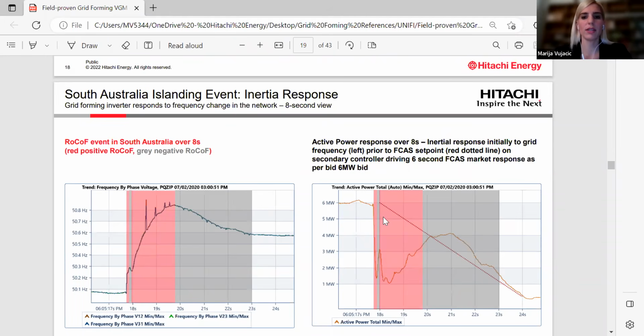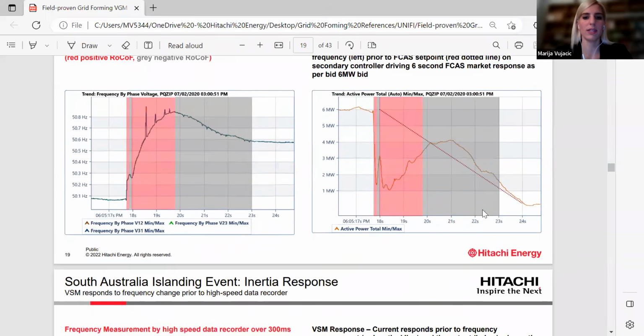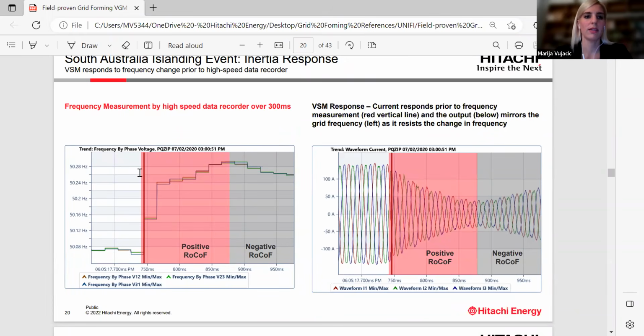What is important to notice here is that this inertia response is quite different to, for example, fast frequency response, because it does not rely on the measurement of the frequency, but provides an instantaneous response to the RoCoF. And this can be seen even better on these slides, because these are measurements taken by a high-speed data recorder. You can see here that the current started decreasing before the increase of the frequency was measured and detected by the control.